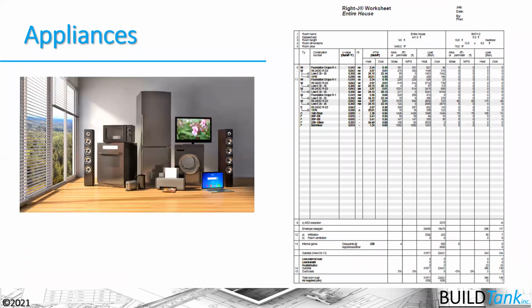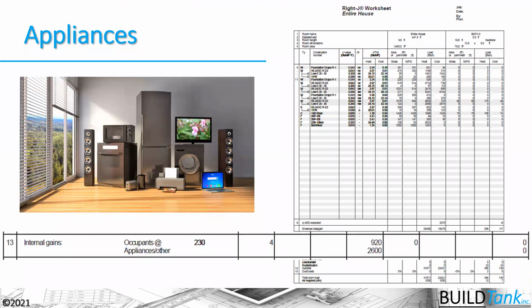Appliance loads are also important to look at. Appliance loads are also defined in these worksheets, and you can see that they added 2,600 BTUs for appliances. Appliances are about 1,300 BTUs per appliance that's added to the system. So you'll usually see about 2 appliances, like refrigerators, added to the HVAC calculation. But if you see 5, 6, 7, you might ask what's going on there.